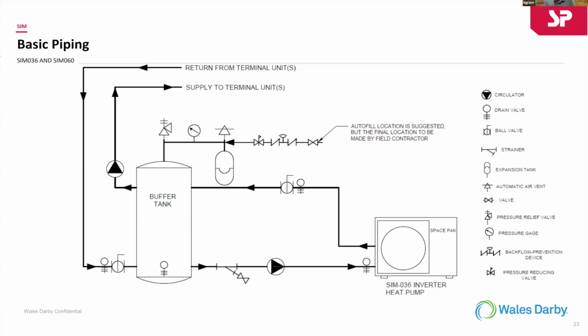Again, it can be as many zones as you want. It doesn't have to be just one zone. It can be 3, 4, however many zones you need. The tanks go in sizing depending on how many BTUs you have. And with these units, you can bank them. You can put 3 or 4 and bank them together, so if you have a house that's bigger than 5 tons, you can bank them and put in a buffer tank to do a larger system. So that can be done.